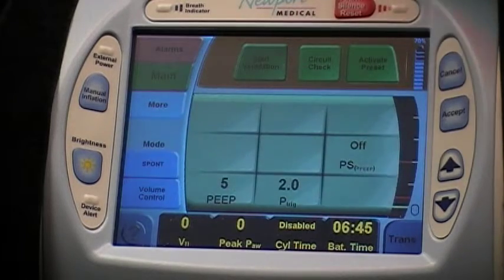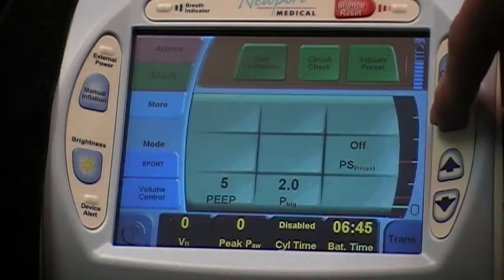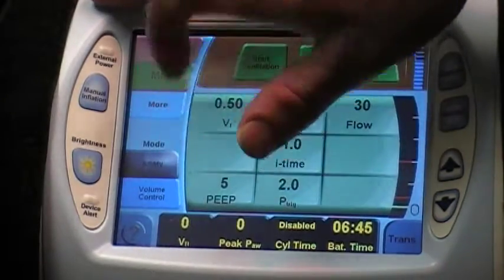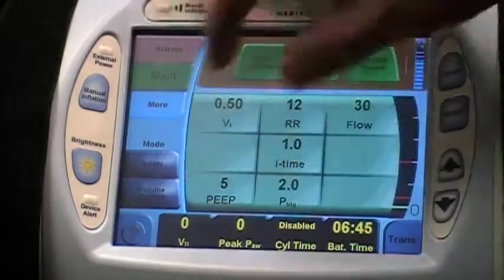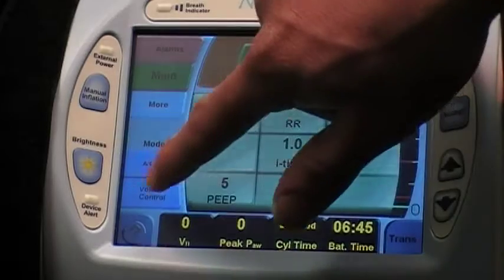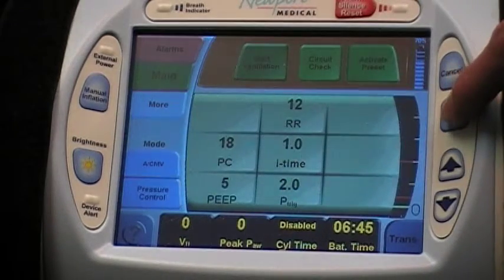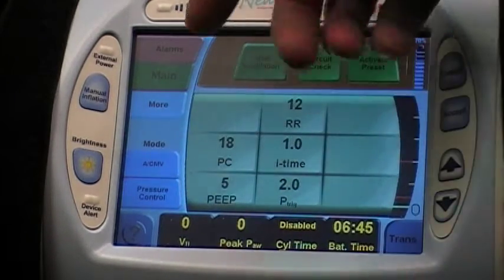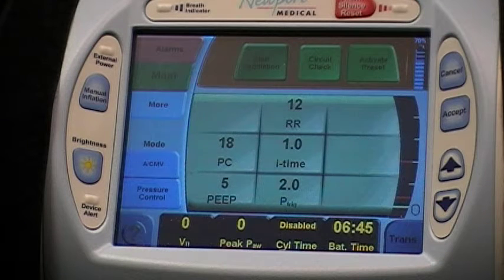Okay, so each time you select a setting on the ventilator, you have to hit accept. For instance, if I want the patient to be in assist control mandatory ventilation, in volume control, I have to hit accept. There's also pressure control, which I can put the patient in. So volume control would be good for an adult patient, and pressure control would be good for a pediatric patient so you do not cause a pneumothorax.